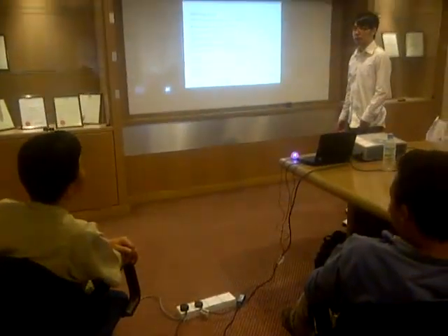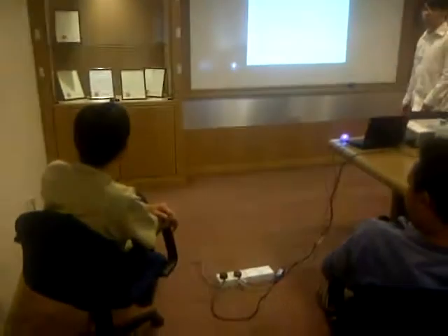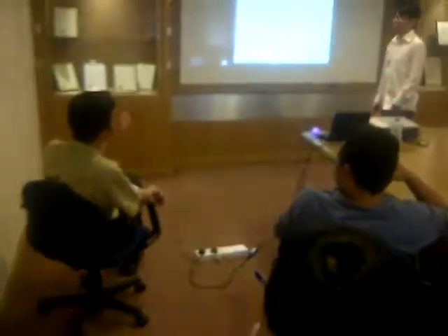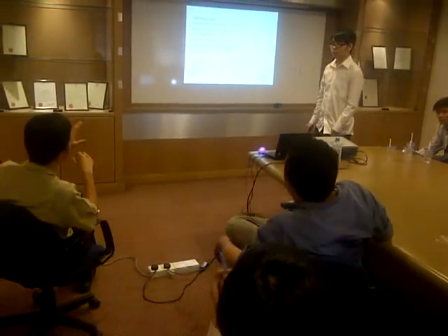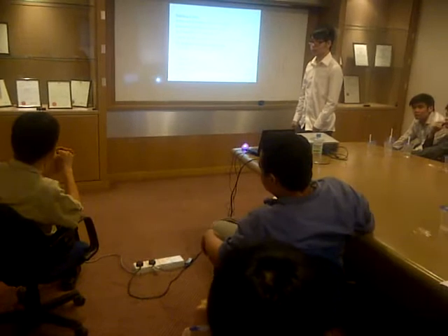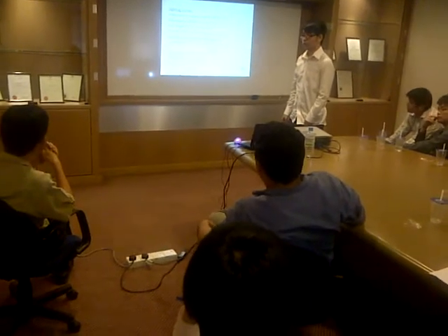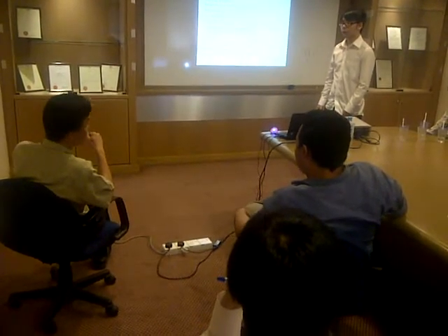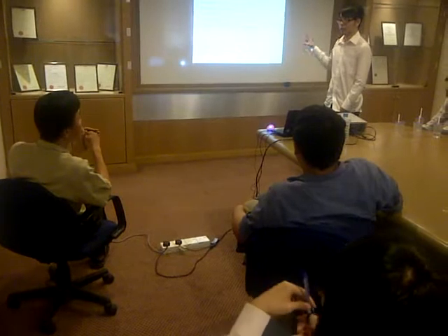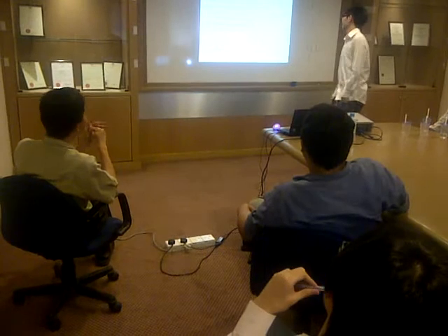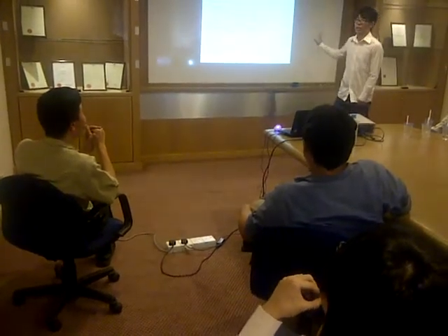They don't have a 20M. 20M is a bit small and normally not very commonly available because nobody buys it, so the manufacturers also don't manufacture it. Normally in the market, people go minimum for RCD, I think minimum is around 30 or 40. The catalog provides 30 and 40, and you cannot find 20M. So if you cannot find it, what do you put? Maybe I just make all the lighting together.